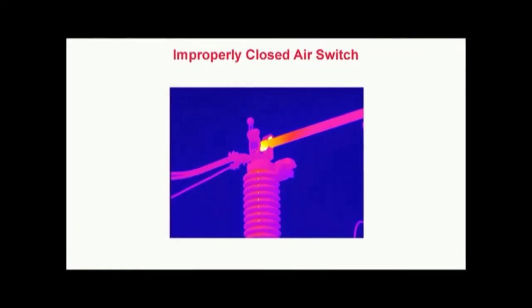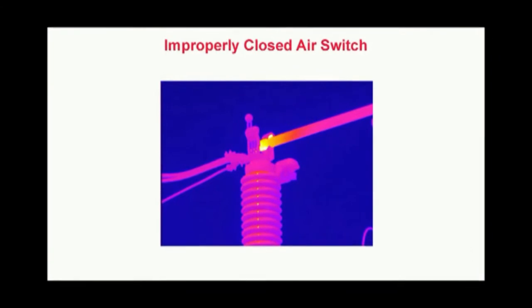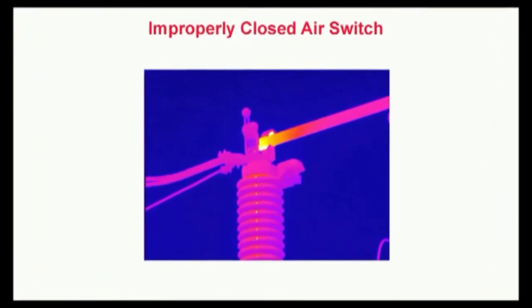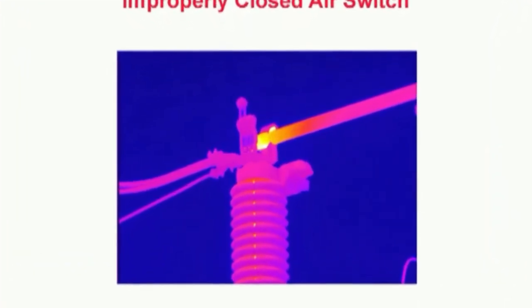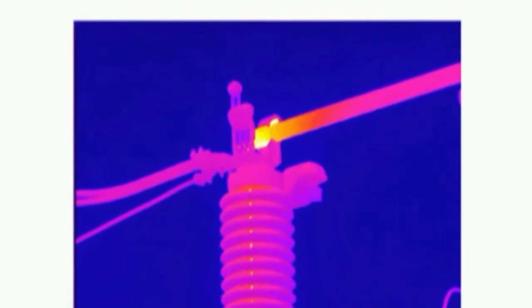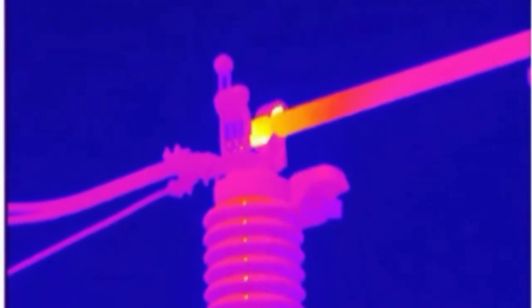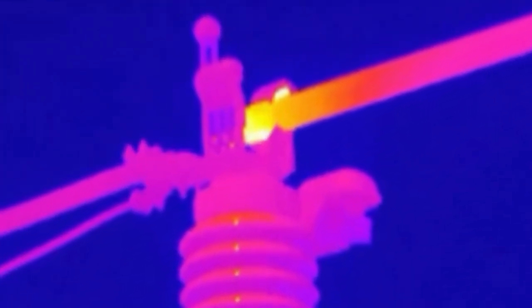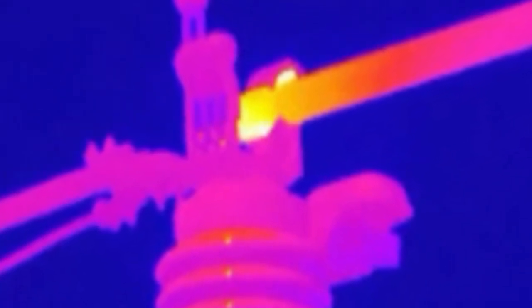Upon further investigation, it was found that the switch was not properly closed. If you look closely, you will see that the contact points on the switch arm are at the 7 and 1 o'clock positions rather than the 9 and 3 o'clock positions, indicating that the switch arm had not rotated fully.